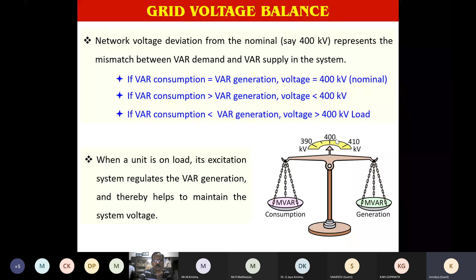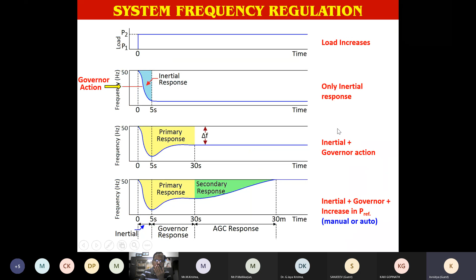Now, these are all inherent with the conventional system, thermal units or hydro units, because we have automatic generation governors, and we also have automatic voltage regulators. But because of the grid connection through power electronic converters, this new device or generating system may not have this. This is the typical frequency regulation. There are various terminologies used, that is primary control, secondary control, etc. These are all available in the case of typical thermal units or hydro units. And the thermal units are actually used for frequency regulation also. But these will not be available with the new systems, because there are two very important parameters which are responsible for maintaining the grid frequency. One is called the system inertia. Second is called droop.